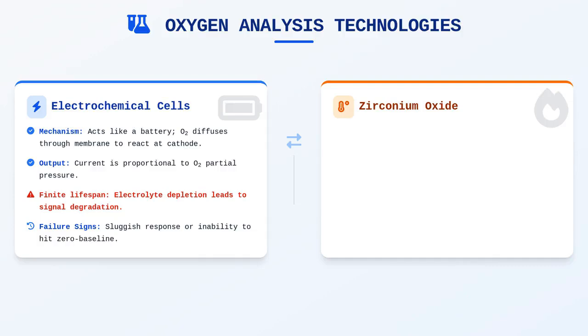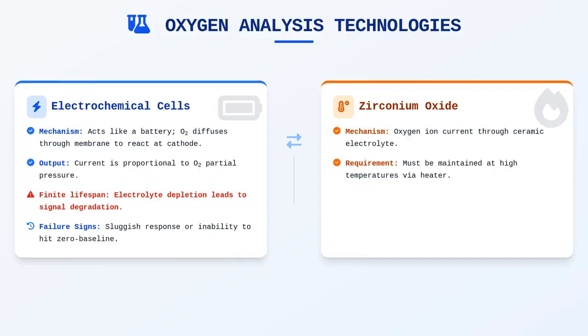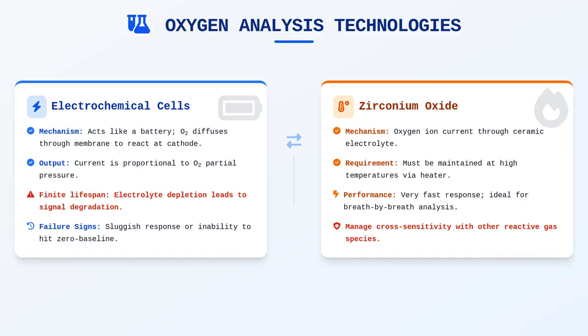Conversely, zirconium oxide sensors operate at high temperatures, creating an oxygen ion current through a ceramic electrolyte. These sensors offer a very fast response time, ideal for breath-by-breath analysis, provided the heater maintains the sensor at the required operating temperature. You must manage cross-sensitivity issues, especially if the sample gas contains other reactive species that might influence the current flow in your sensors.